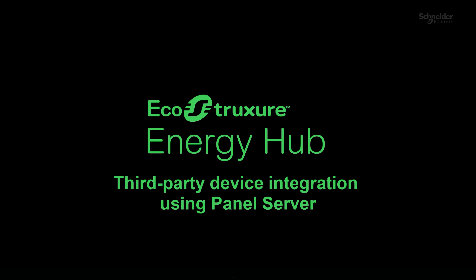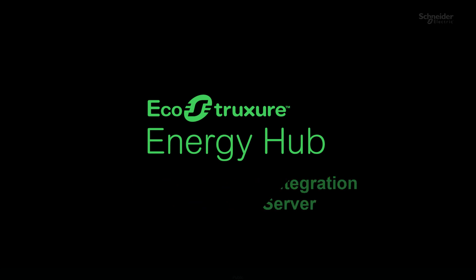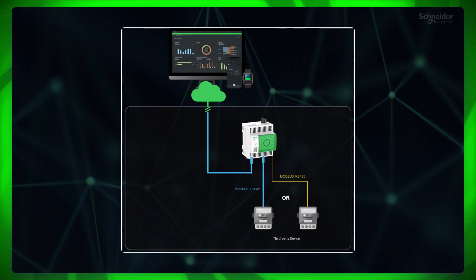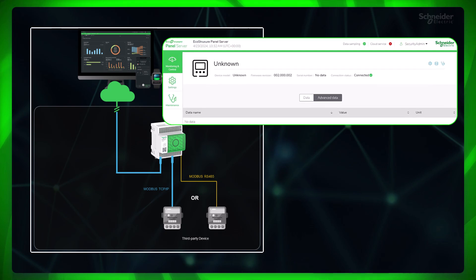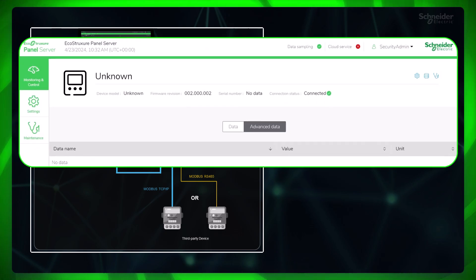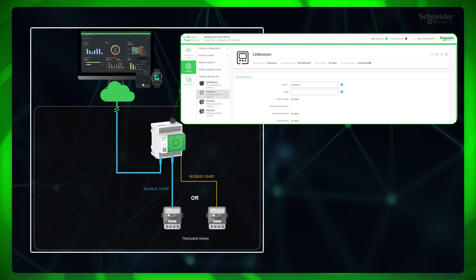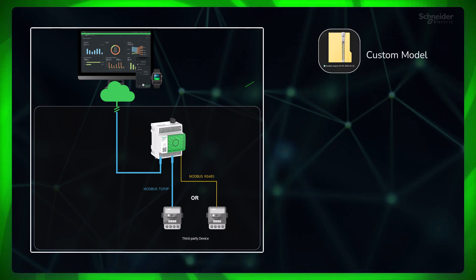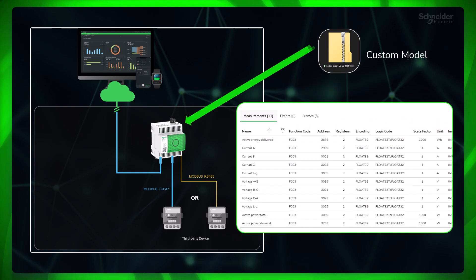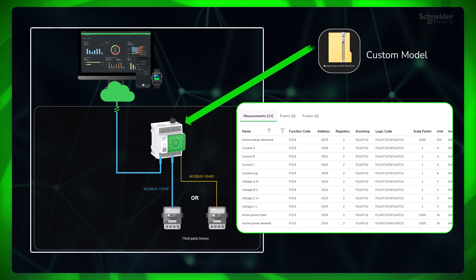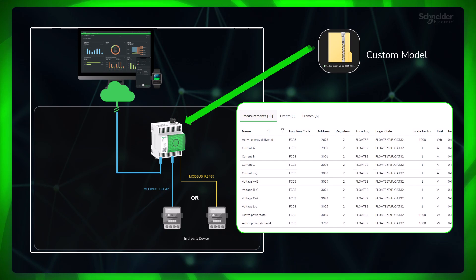In EcoStruxure Energy Hub using custom models for EcoStruxure Panel Server, Panel Server does not provide native support for certain Schneider and other third-party Modbus devices. It may appear as unknown, or may not even be visible on the web page. So for integrating these devices to Energy Hub, a custom model needs to be created for Panel Server. The custom model is a configuration file that maps device measurements, allowing Panel Server to communicate with third-party devices.